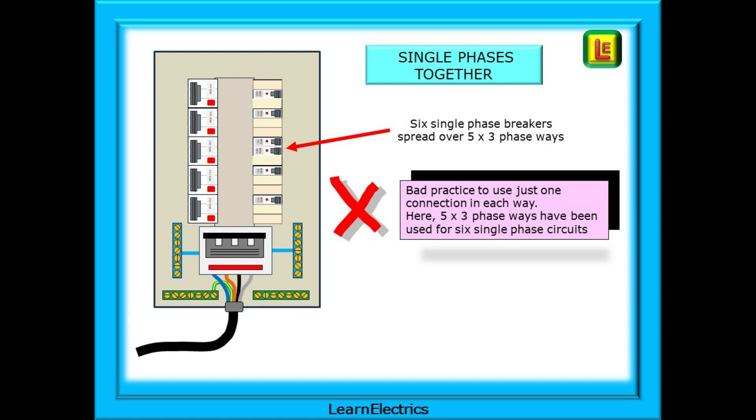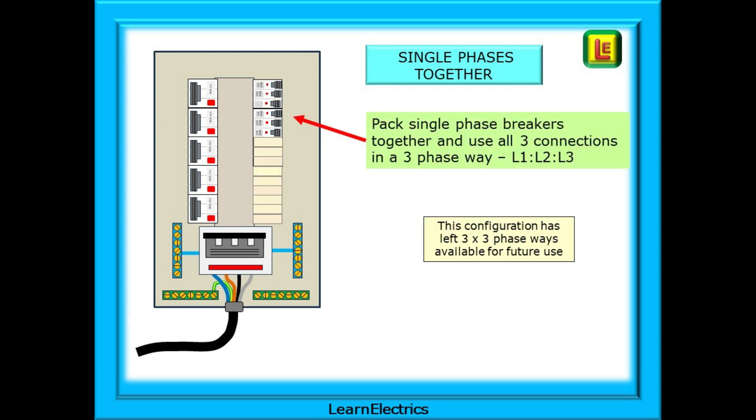Good working practice says that we should try to keep single phases together. Here, we have six single-phase circuit breakers spread over five three-phase ways. As we said, it's bad practice to use just one connection in each way. If we want to add a three-phase breaker to the circuit, where is it going to go without moving things around? Far better to pack single-phase breakers together and use all three connections in a three-phase way, L1, L2 and L3, and then move on to the next way. By wiring to this configuration, we've left three three-phase ways available for future use and expansion.